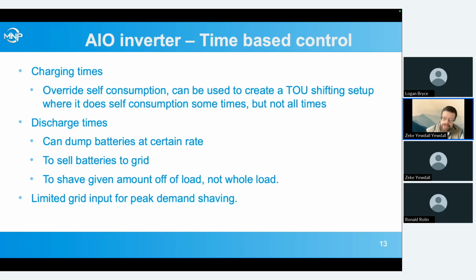If we want to, say, top the batteries off right after the end of peak demand times, what we would do is turn on grid charging for a charging time after 8 p.m. Right now, we're still working on this in the firmware, and it's not in the current version, but we're working on a version where you'll be able to set during this time period, I want to not only charge, but I want to charge from the grid, not just from solar. That would let you immediately top off your batteries after the end of peak demand times rather than waiting for the next day for the sun to come up. So a little more flexibility. Right now, it's not quite as flexible, but that's some of the future features we're working out in new firmware.